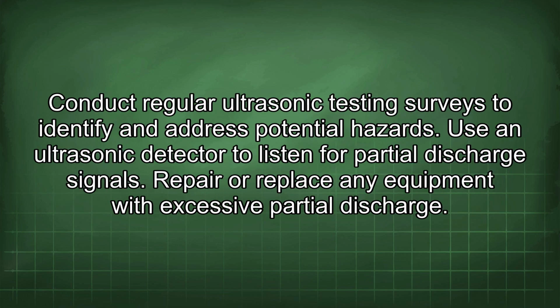Conduct regular ultrasonic testing surveys to identify and address potential hazards. Use an ultrasonic detector to listen for partial discharge signals. Repair or replace any equipment with excessive partial discharge.